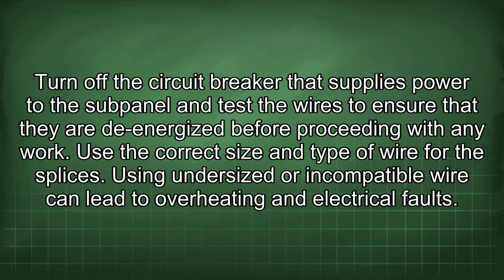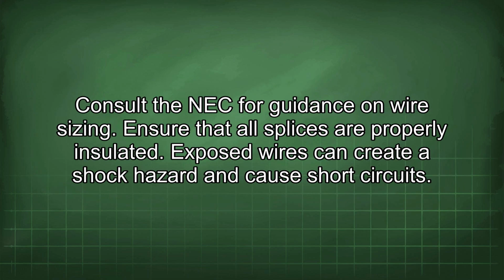Turn off the circuit breaker that supplies power to the subpanel and test the wires to ensure that they are de-energized before proceeding with any work. Use the correct size and type of wire for the splices. Using undersized or incompatible wire can lead to overheating and electrical faults. Consult the NEC for guidance on wire sizing.